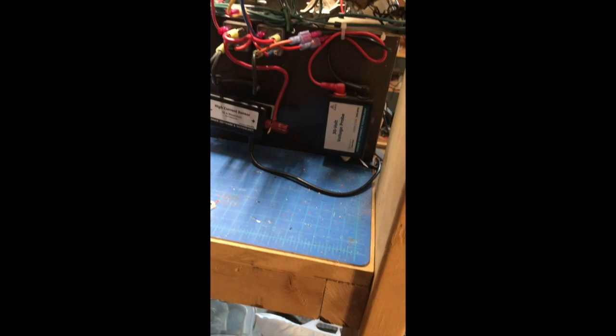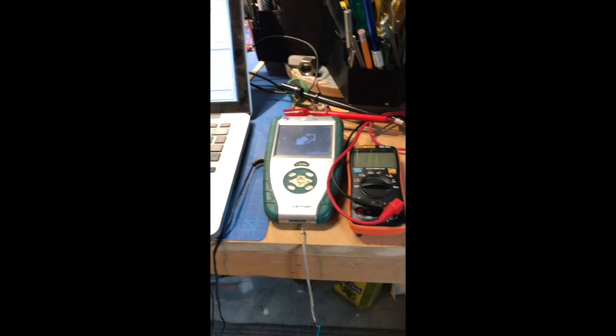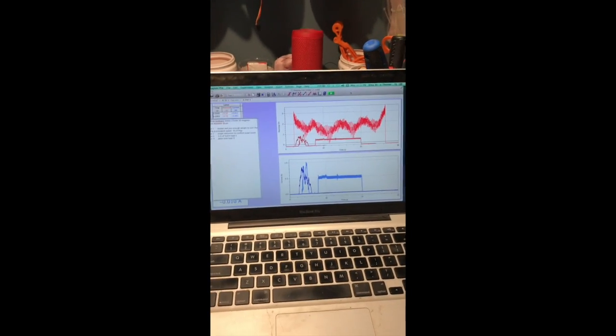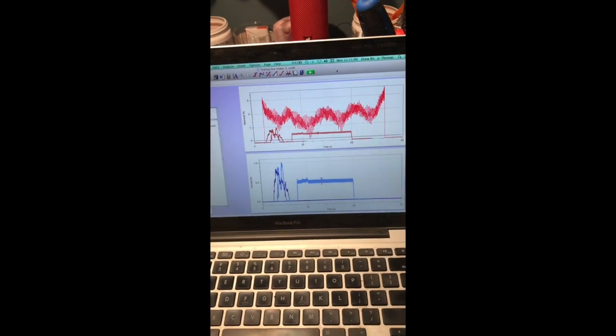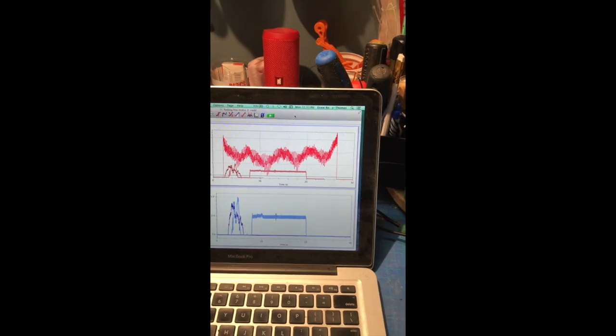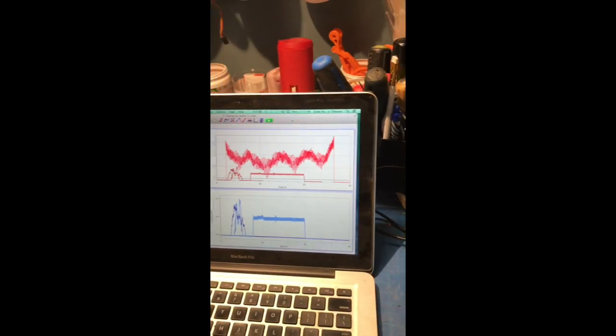And that's all recorded over here. These two probes, one obviously current, one voltage, are read by this little box and USB'd into my old laptop. At this point I have the sampling set at about 5,000 samples per second, so it produces a pretty accurate oscilloscope-like model, and I can regraph it in all kinds of ways. This data logging software is very handy in all this.